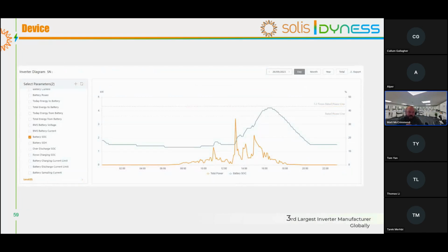When we pull information from the inverter, we can actually plot it on a graph. This is very useful when it comes to fault finding, especially with hybrid systems. We have a number of different things that we can look at and compare. You can select multiple variables on the left-hand side, and then select which day it is. If you select month and year, it will dramatically reduce what you can actually see. It will be more general information. But if you're looking for specific information on the inverter, you have to go per day, and then change the variables on the left-hand side.